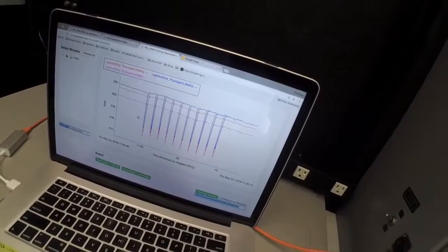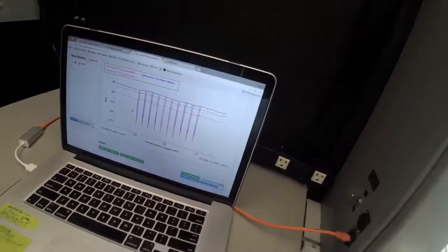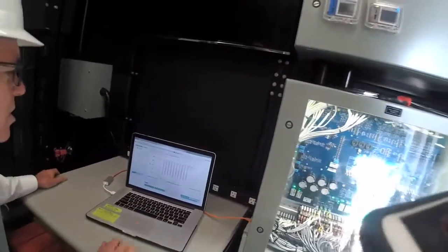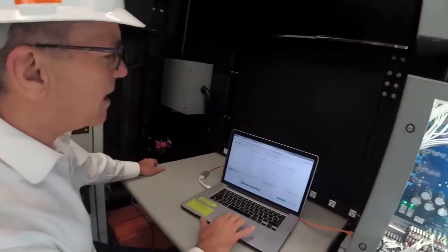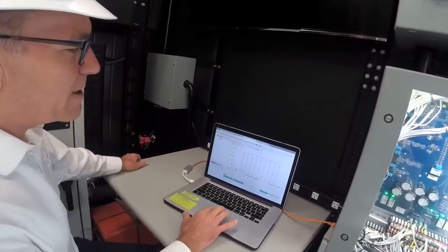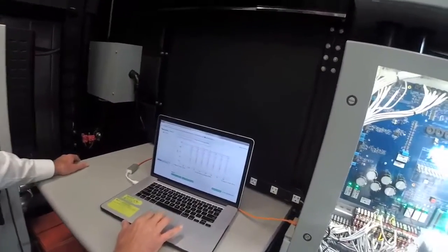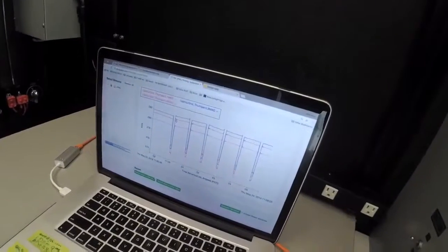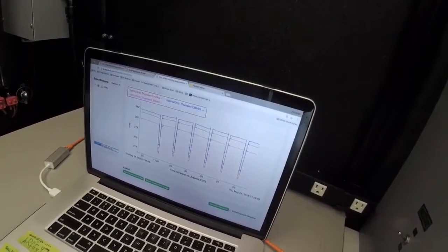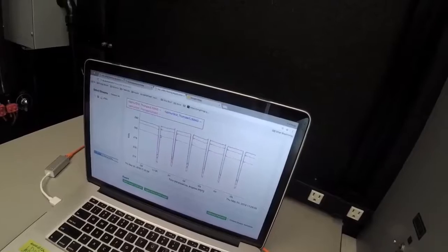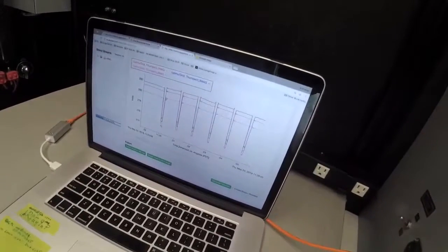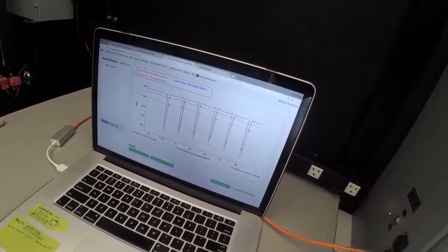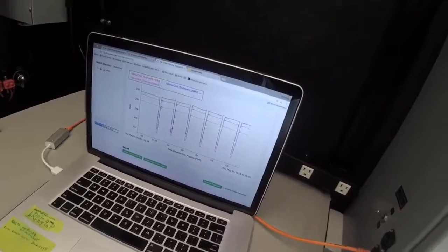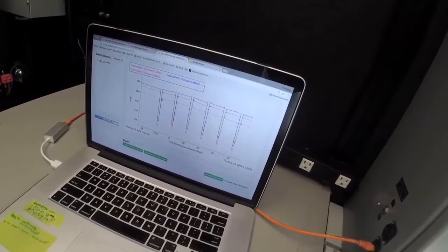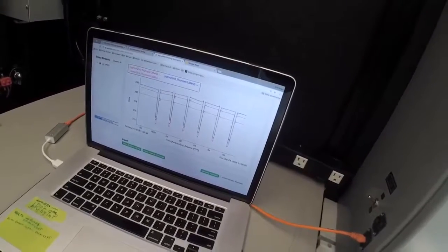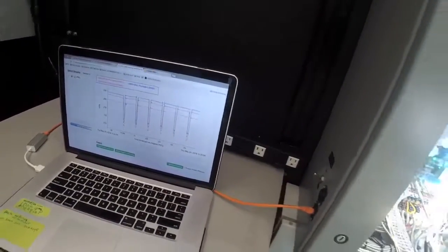These signals can propagate throughout an entire microgrid, or in many cases even for miles across a distribution grid. What's of interest in terms of analysis is what happens during the transitions. You can see oscillations occurred at the end of each pulse. The characteristics of those oscillations determine the stability of this segment of the grid, and with proper analysis can assure a facility owner that the system will be available during an emergency when they really need it.